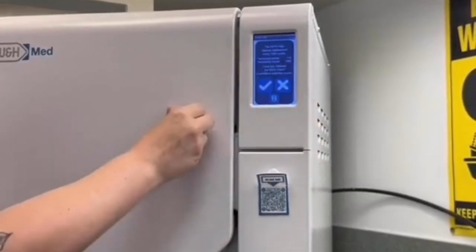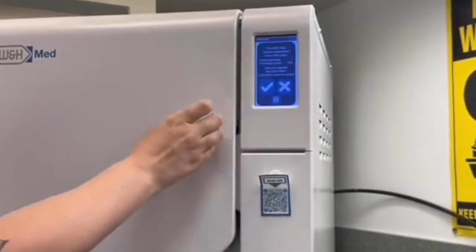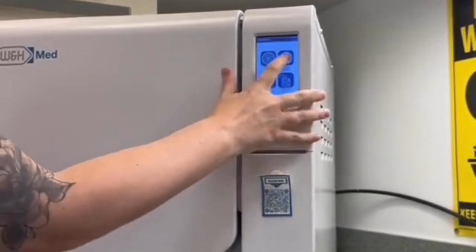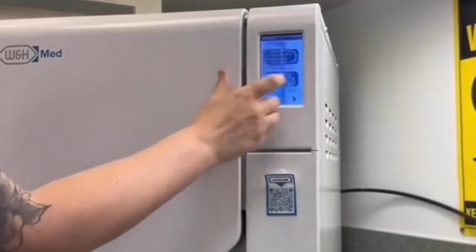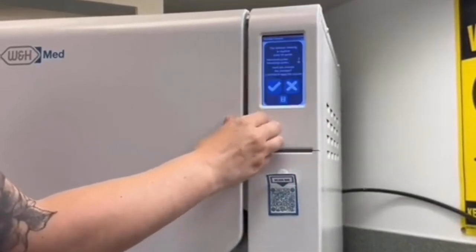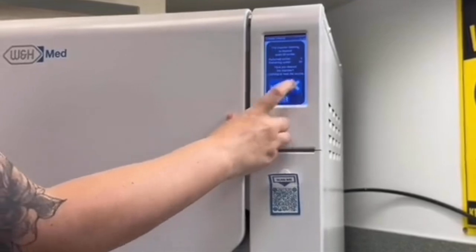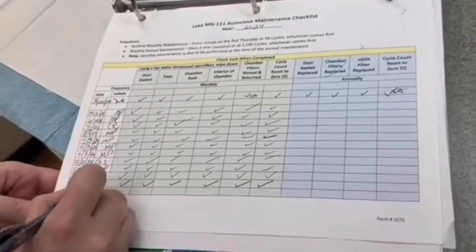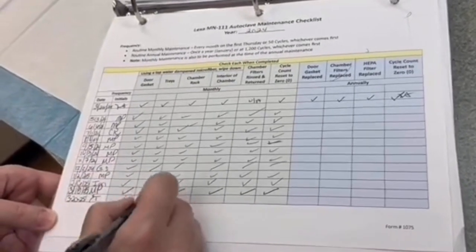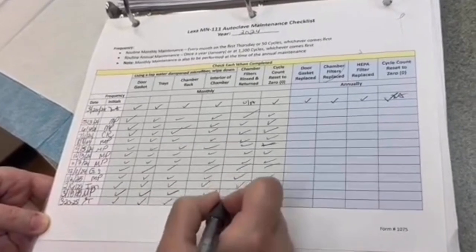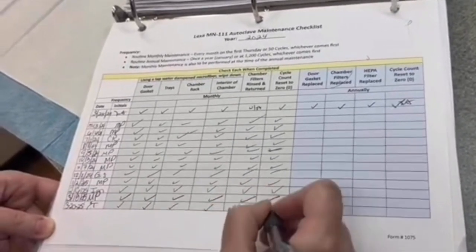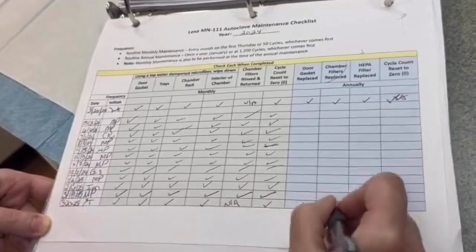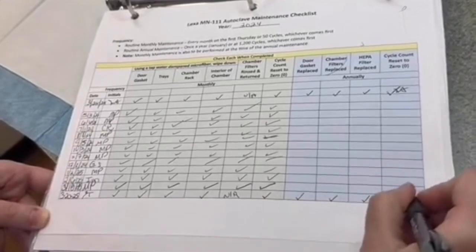On the main screen, select Maintenance, then be sure to clear the HEPA filter, the door gasket, and finally, the chamber cleaning by selecting the check mark to reset the count. To confirm each area was reset, select each one again to view the count as 0. Now it is time to document the annual maintenance. You will note the date, your initials, and check off all the monthly tasks and the annual tasks.